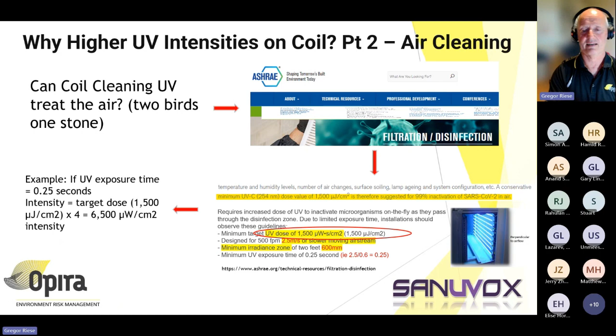specifically for COVID-19, 99% inactivation, you need a 1500 microjoules dose, and you can do the back of the envelope math on that. So the airstream must be slower than 2.5 meters a second, which most air handlers are moving less than that, and you need an irradiance zone of 2 feet or 600 millimeters. And so you get a minimum exposure time of a quarter of a second.